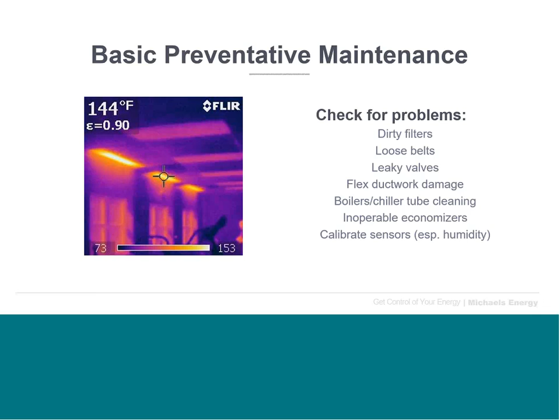So there's other things like fixing flex ductwork damage and boiler and chiller tube cleaning, fixing economizers and outdoor air damper controls, and looking at sensors, particularly humidity sensors. We see those are big trouble sensors. CO2 sensors also tend to have a high failure rate. So those sensors, if they're used in important calculations or as part of an important sequence within the control system, incorrect sensor readings there can lead to some degradation in the energy performance of the building.